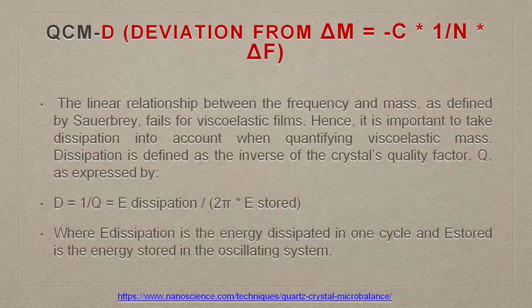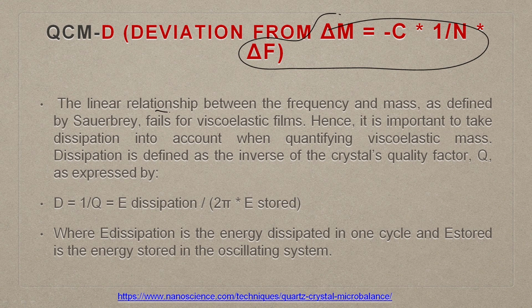Now, QCM-D is a deviation from the classic Sauerbrey equation. The linear relationship between frequency and mass as defined by the Sauerbrey equation fails for viscoelastic film. Hence, it is important to take dissipation into account when quantifying viscoelastic mass. Remember this word, viscoelastic mass.